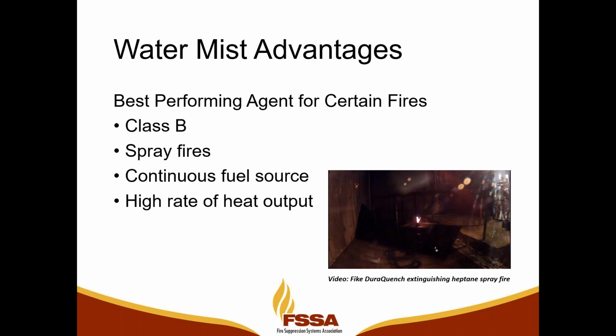And another advantage of water mist is that it is just the ideal agent for certain types of fires. It's the best performing agent for certain types of fires. And these are typically Class B liquid flammable fires, especially spray fires where we might have a continuous fuel source. And you can think in terms of a ruptured hydraulic line or a ruptured fuel line, say on a diesel generator, where we're going to have a very hot spray fire with a high rate of heat output. The hotter the fire, the more quickly the water vaporizes, the more quickly it absorbs the heat of the fire, inerts the space right around the flame front, and puts out the fire.